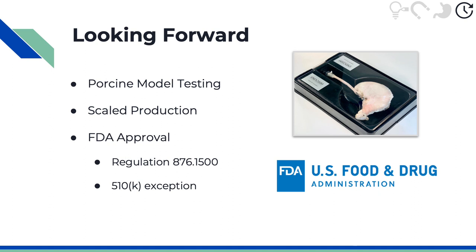We plan to make the Endomagno stiffer with an outer coating such as an endoglide sheath, with lengths of 5 feet and 8 feet for different types of endoscopes. Finally, we plan to patent and license Endomagno to medical device companies and obtain FDA approval based on guidelines for endoscope accessories.